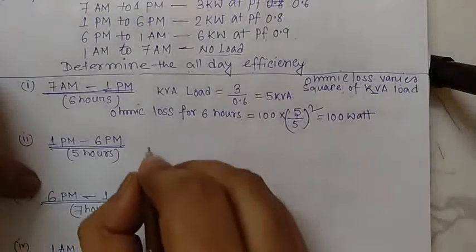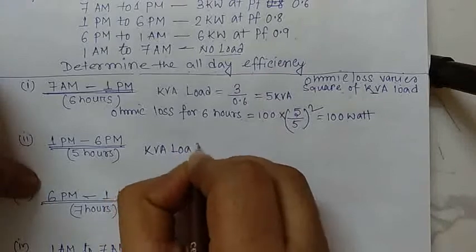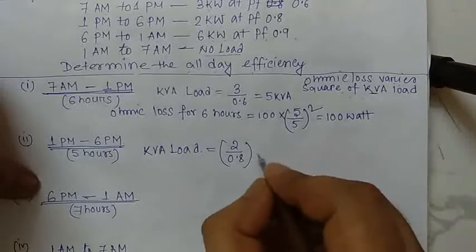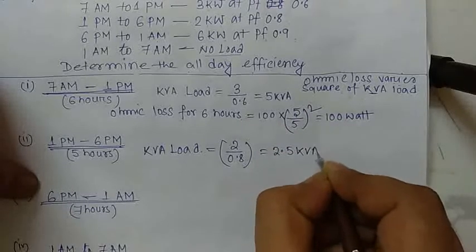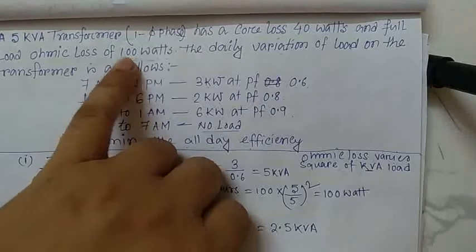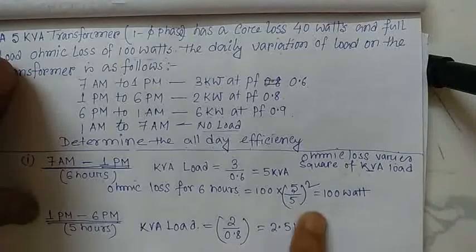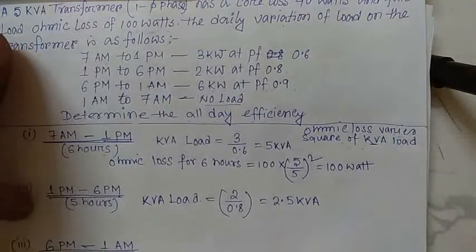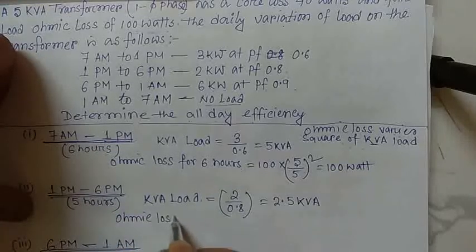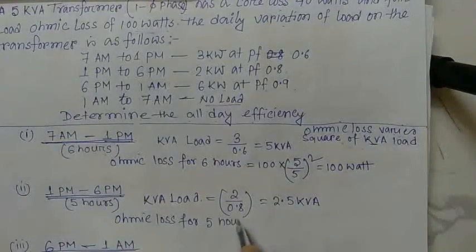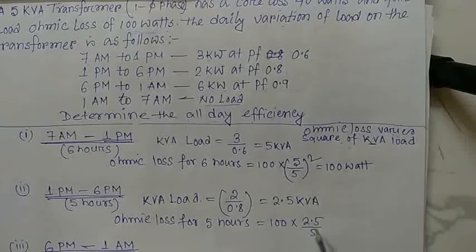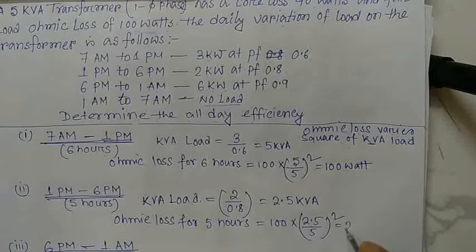For 1pm to 6pm (5 hours), the kVA load is 2 kilowatt divided by 0.8 = 2.5 kVA. Since full load ohmic loss is 100 watts at 5 kVA, the ohmic loss for these 5 hours is 100 × (2.5/5)² = 25 watts.